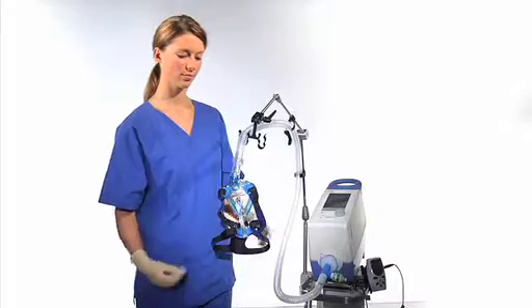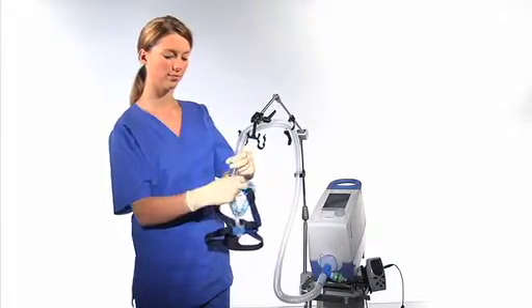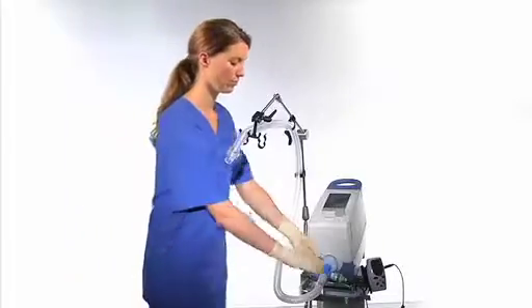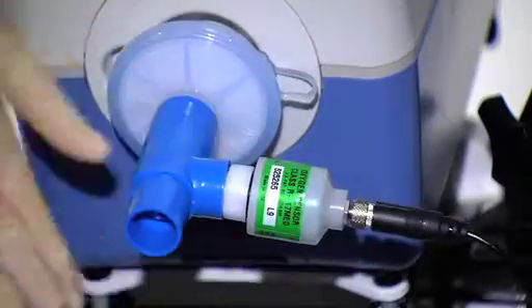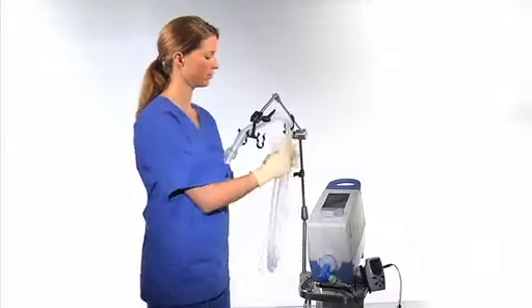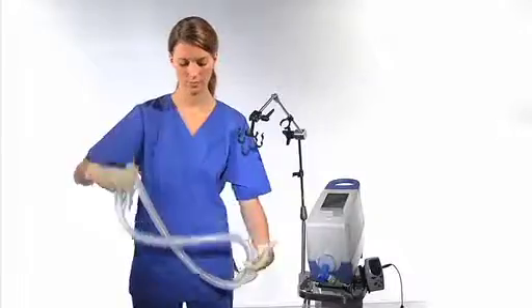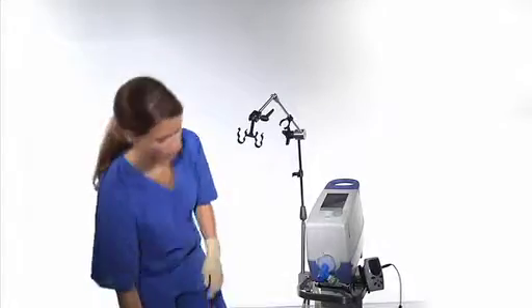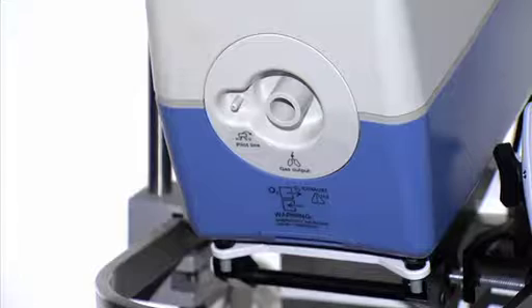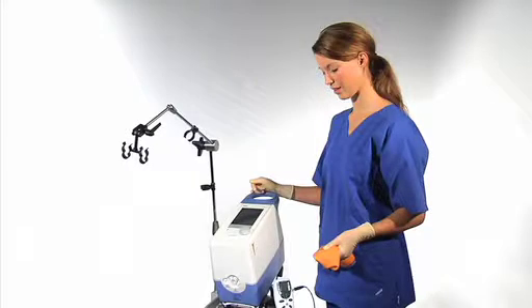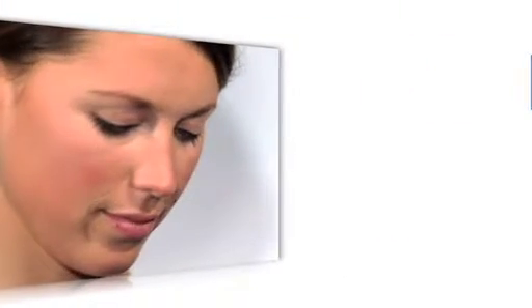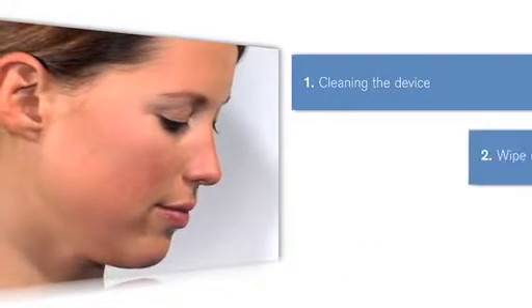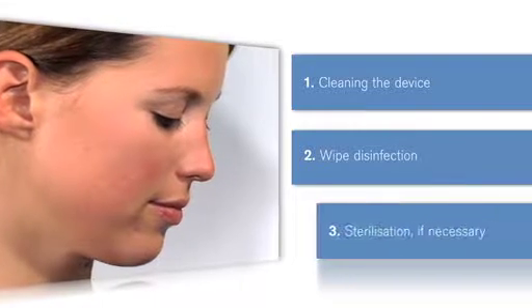Please start by removing the mask, the leak valve circuit and the filter. The reusable NovaStar mask immediately goes into the hygiene procedure. The filter and the leak valve circuit are for single patient use only. Then begin the cleaning process. Remember the 3 steps of hygiene: cleaning the device, wipe disinfection, sterilization if necessary.